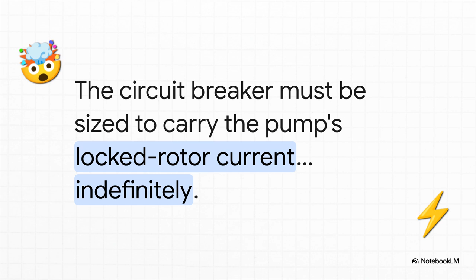So let's put some real numbers on this from the example in our source material. For a pretty standard 50 horsepower fire pump, the circuit breaker that's installed is a massive 800 amp breaker. Okay? Remember that number, 800 amps. Now get this. What kind of wire is that 800 amp breaker protecting? It's a number 3 gauge wire, which is only safely rated to handle about 100 amps, maybe a little more depending on the conditions. So wait a minute. An 800 amp breaker on a 100 amp wire? How does that make any sense? What is going on?